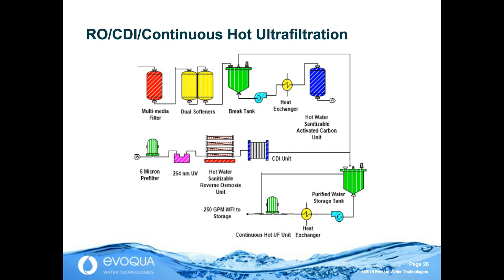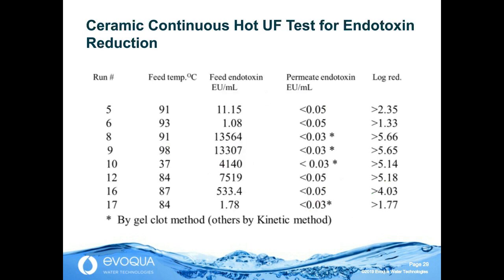The test results here are not from this system. This is a major test run by a leading pharma company to test ultrafiltration. If you look in the center column at feed endotoxin, there's endotoxin at times over 13,000 EU per mL. That was created. You'll never find that in a water system. The system was designed to concentrate up endotoxin, but every test that they ran was below the limit of detection, and at times a greater than 5 log reduction of endotoxin, and this is also achievable with other types of ultrafilter elements.